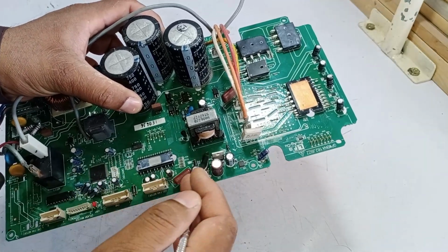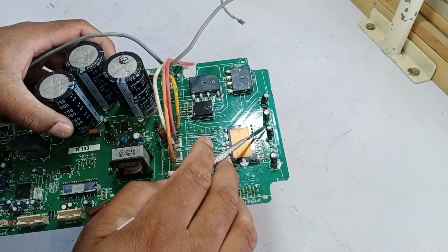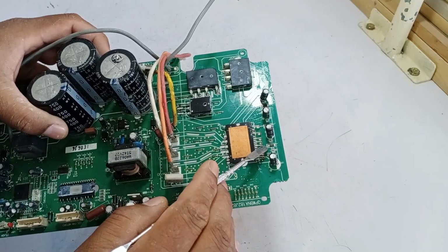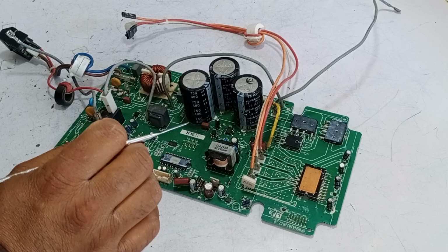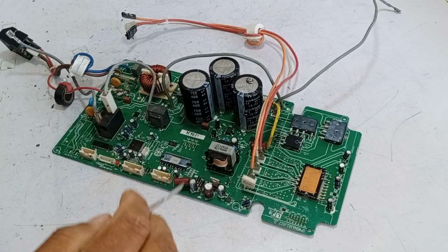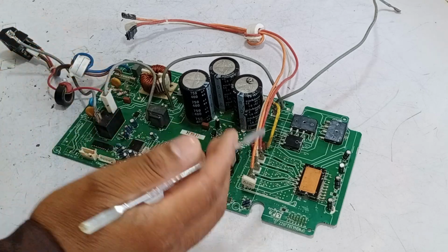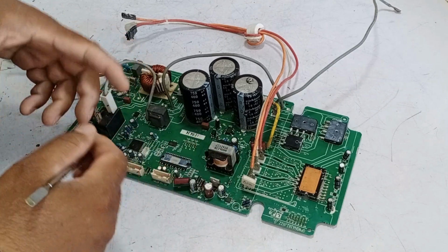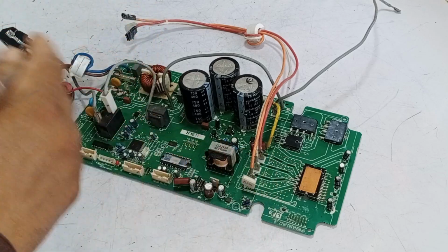However, such issues are less common because most faults occur in the high-side circuitry or the capacitors involved in the feedback system. From my experience, the compressor windings often fail, or the compressor itself becomes locked or jammed, leading to this error. But remember, the PCB issues described earlier can also cause the same problem, as explained. So, these are the key points to investigate for diagnosing and resolving the error.